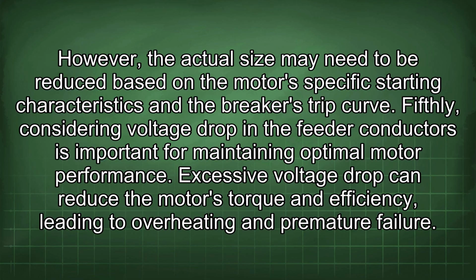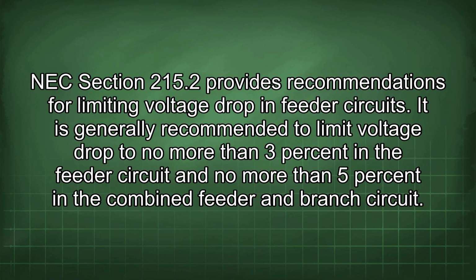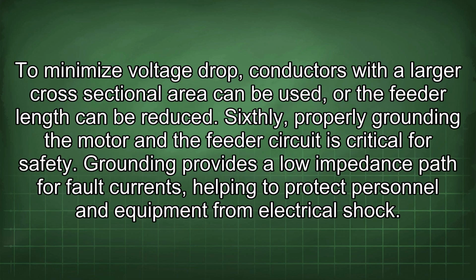curve. Fifthly, considering voltage drop in the feeder conductors is important for maintaining optimal motor performance. Excessive voltage drop can reduce the motor's torque and efficiency, leading to overheating and premature failure. NEC Section 215.2 provides recommendations for limiting voltage drop in feeder circuits. It is generally recommended to limit voltage drop to no more than 3% in the feeder circuit and no more than 5% in the combined feeder and branch circuit. To minimize voltage drop, conductors with a larger cross-sectional area can be used, or the feeder length can be reduced.